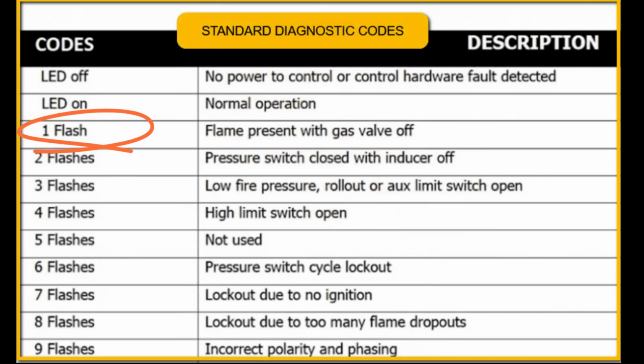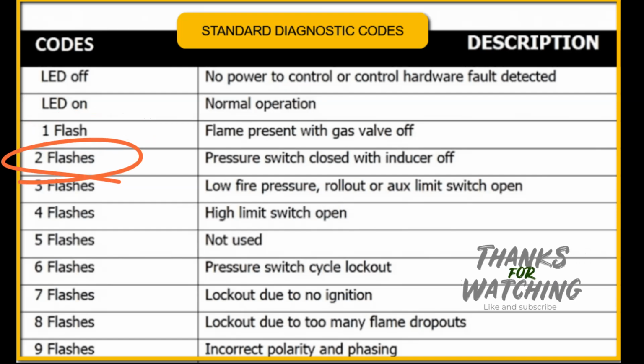If you see this, it would generally be cause to call a professional, as it may be a fault with the board or the gas valve. Reset the furnace first to try to avoid the service call. If you have a pressure switch code, it is almost never the pressure switch that is at fault. Check the exhaust and intake pipes. Check for blockages and restrictions.